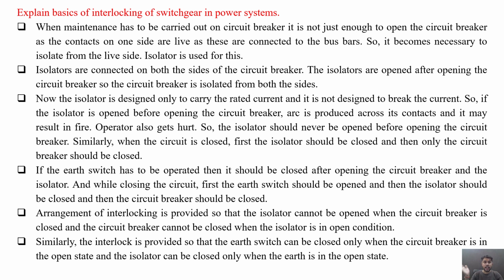Isolators are connected on either side, that is, both sides of the circuit breaker. The isolators are opened after the opening of the circuit breaker. So the circuit breaker is isolated from both the sides.